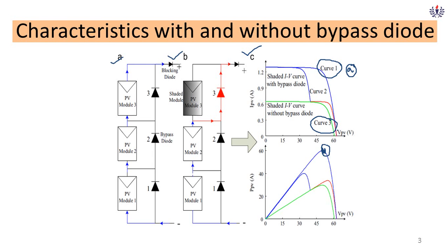To avoid this, we are going to connect a bypass diode. This bypass diode concept we have already explained in the previous lectures. If you are using these three modules in shaded condition, the PV module receiving lower irradiation, or a difference in irradiation condition, will tend to produce a reverse voltage, plus and minus. This reverse voltage will make the diode forward biased, and PV module 2 and PV module 1 are in operation, in the sense 40 volt can be taken. For example, 20 plus 20.